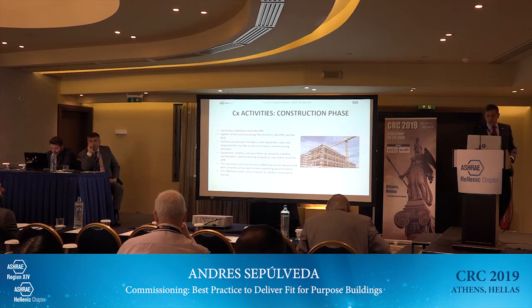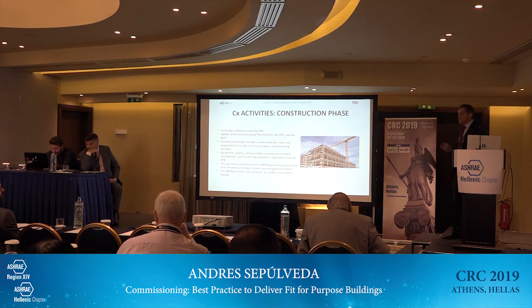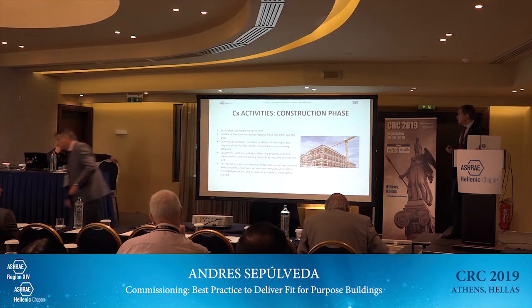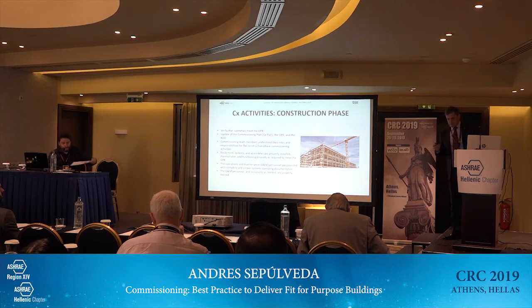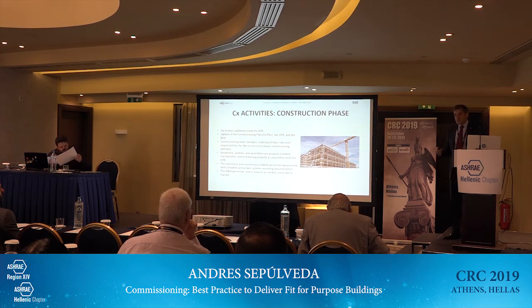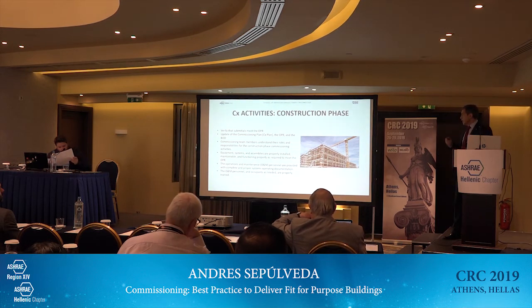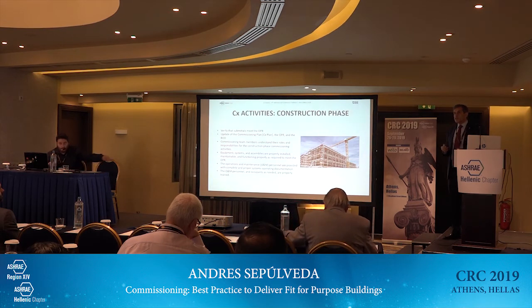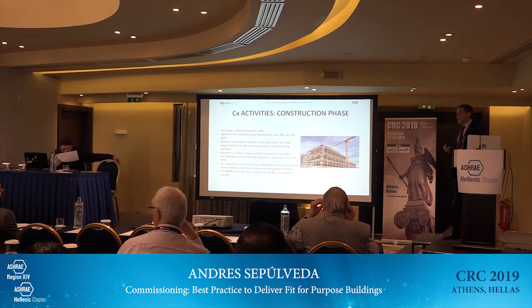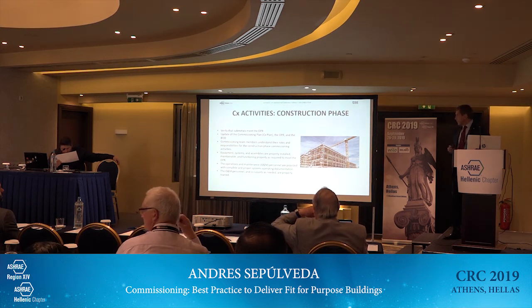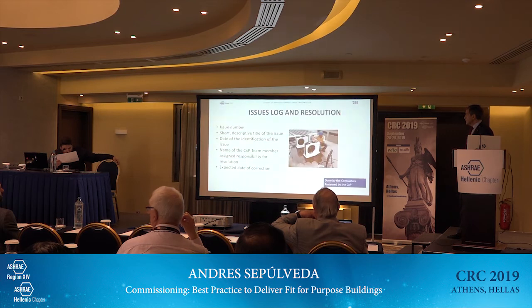Commissioning activities during the construction phase: submittals must be verified to meet the owner project requirements. The commissioning plan, the OPR, and the BOD need to be updated during this phase. It's important to verify that the systems and assemblies of the building are properly delivered, installed, tested, operated, and maintained according to the OPR, that operation documentation is delivered to the O&M staff, and that this staff is well trained to manage the building.